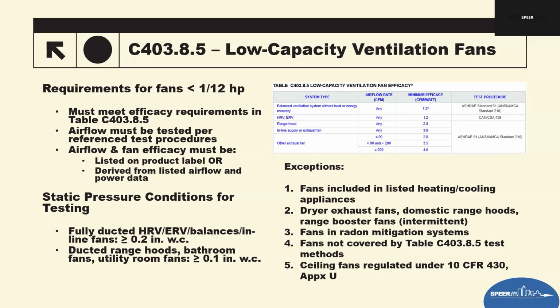Code sets minimum static pressures to be used for testing as 0.2 inches of water column for fully ducted ERVs or HRVs, balanced systems, or inline fans, and then a 0.1 inch of water column for ducted bath fans, utility fans, and ducted range hoods.